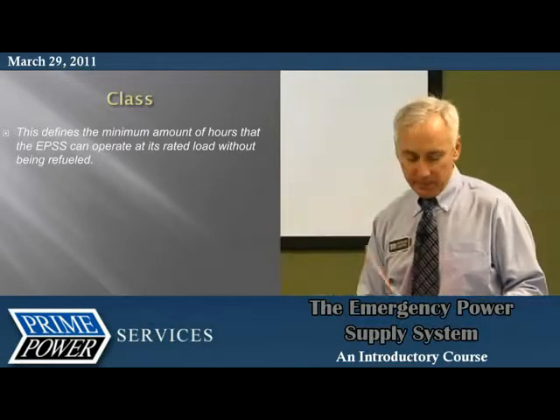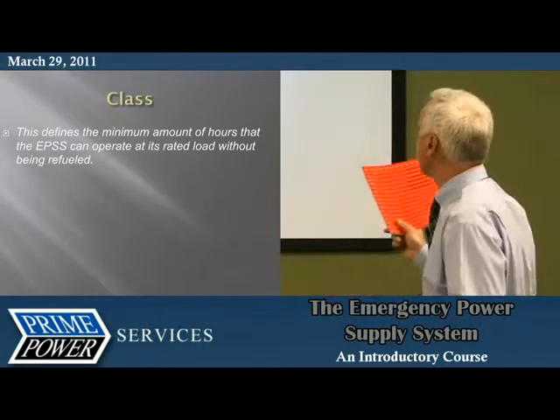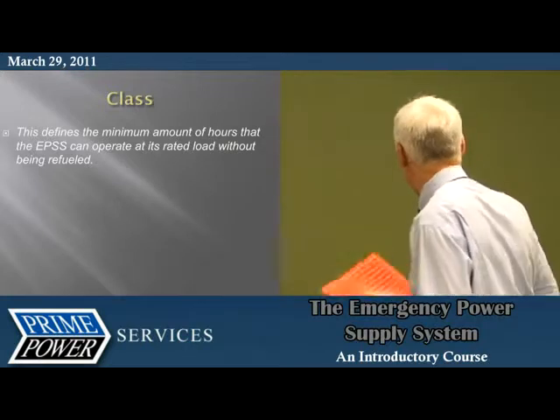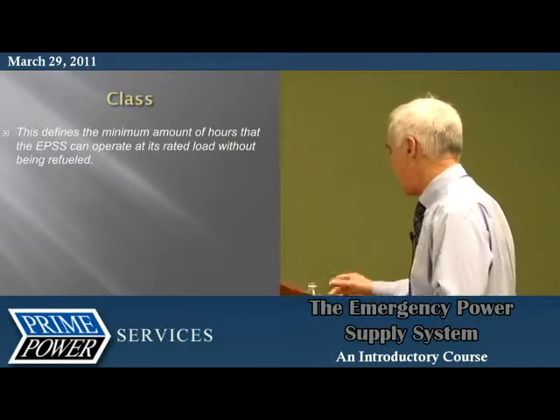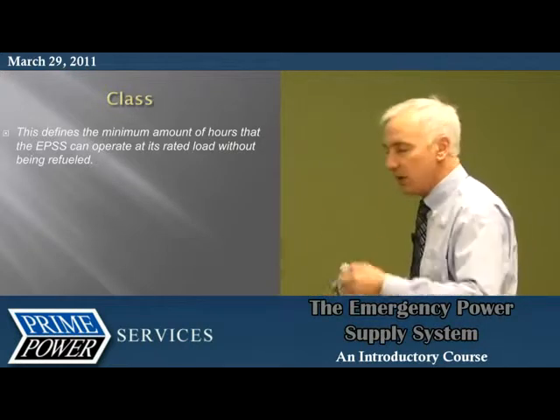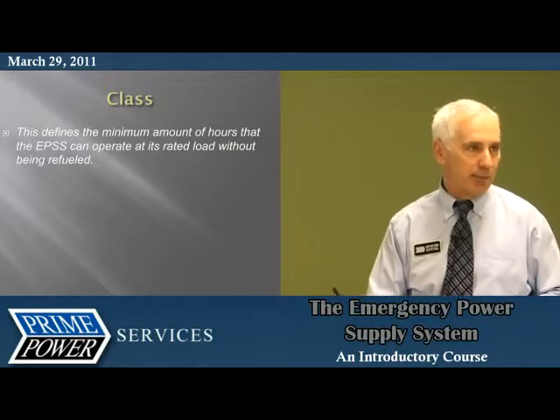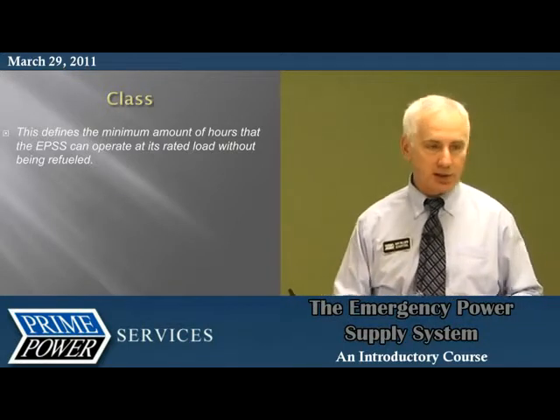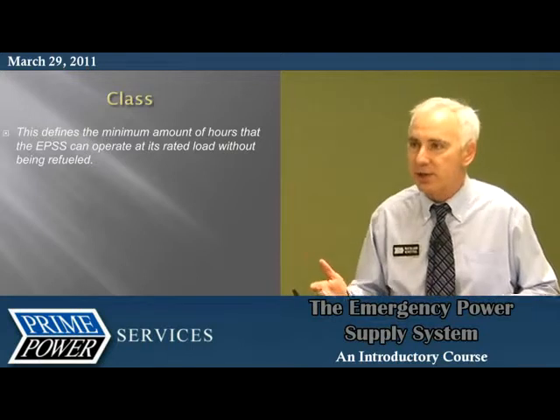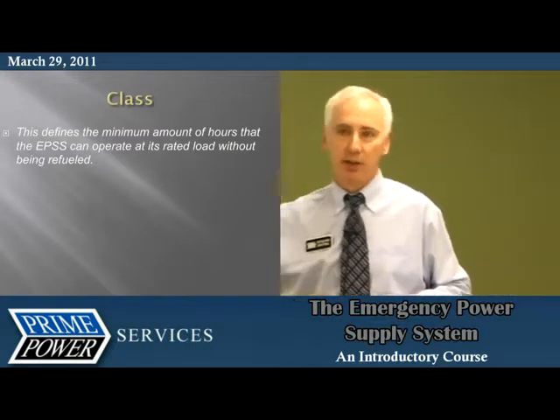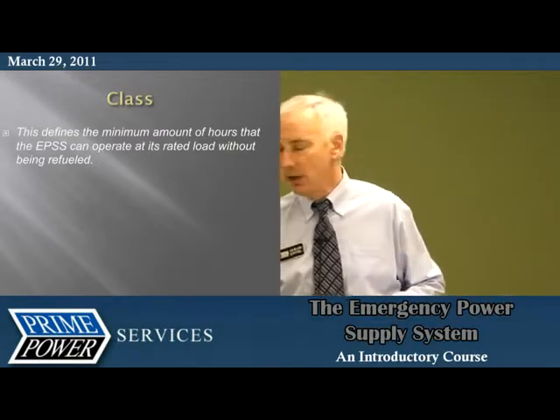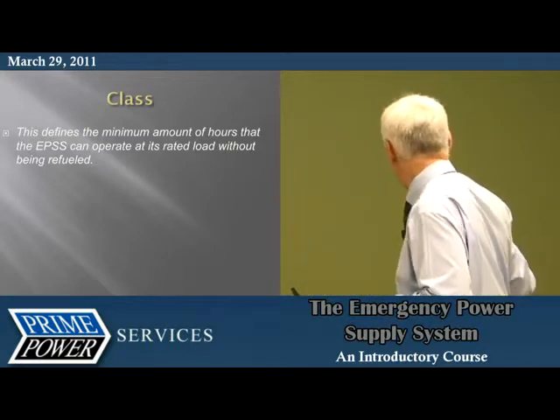They define emergency power systems based on class, which is how long it has to run. With hospitals nowadays, it's 72 to 96 hours. Most applications in a building, the fire marshal just says you need to be able to empty out the building, so it could be just a couple hours. This is how much fuel you have to have on site.